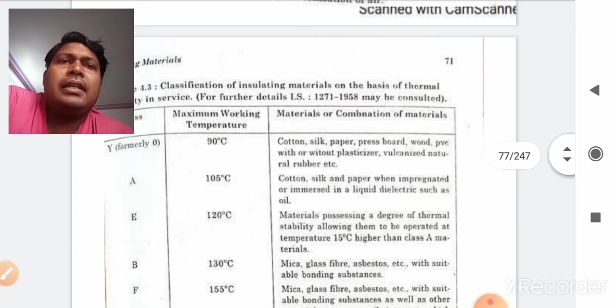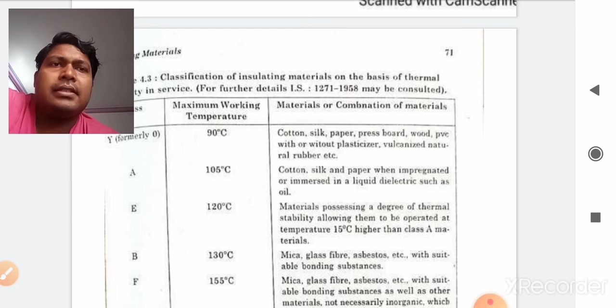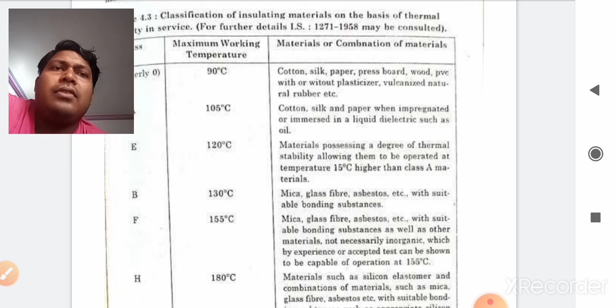Now the other classes are A, E, B and F, as well as H and C. Now we will discuss A. The working temperature of class A is 105 degrees. Its material is cotton, silk, paper, when impregnated or immersed in a dielectric such as oil. Now class E is an insulation which can withstand a working temperature of 120 degrees centigrade. The materials possess a high degree of thermal stability, allowing them to be operated at a temperature 15 degrees higher than class A material. Similarly students, B has 130 degrees centigrade, F has 155 degrees centigrade, as well as H having 180 degrees centigrade, and class H type of insulation will provide you 180 degrees centigrade, and the materials used are correspondingly written.